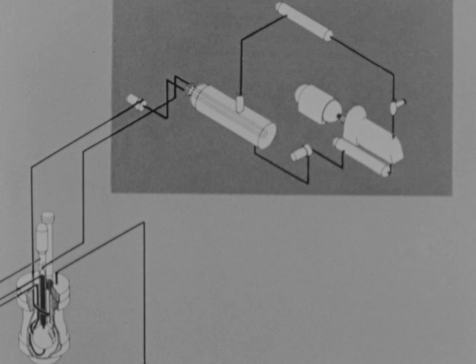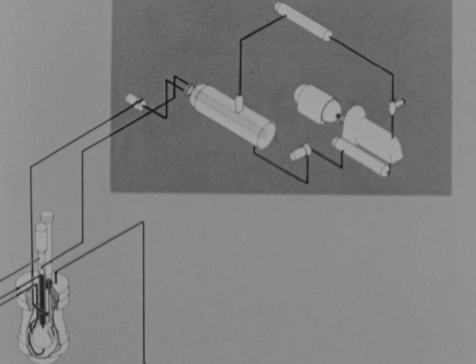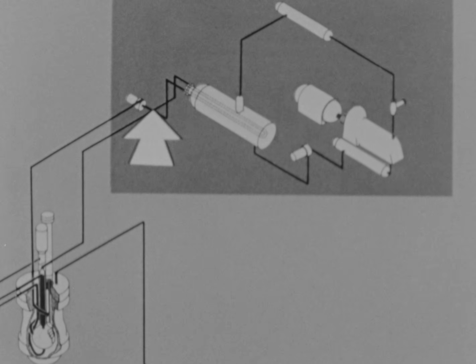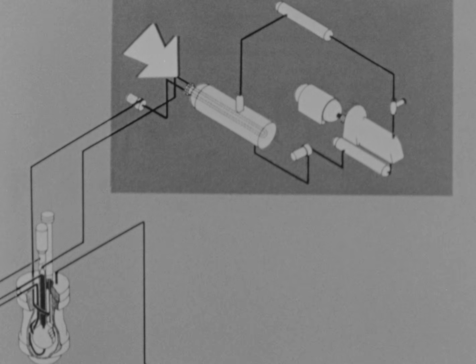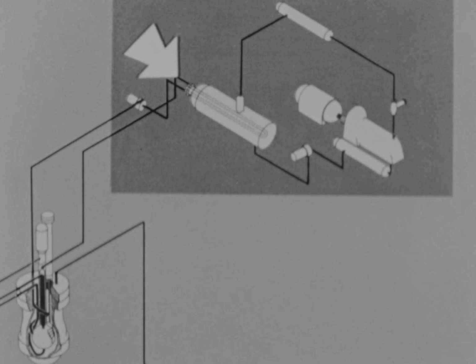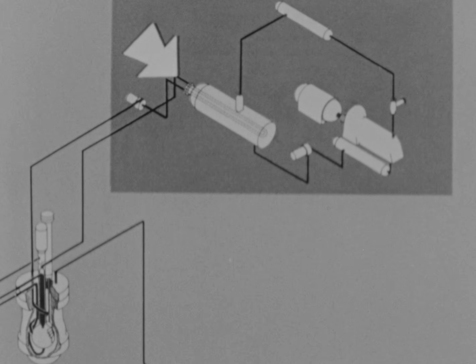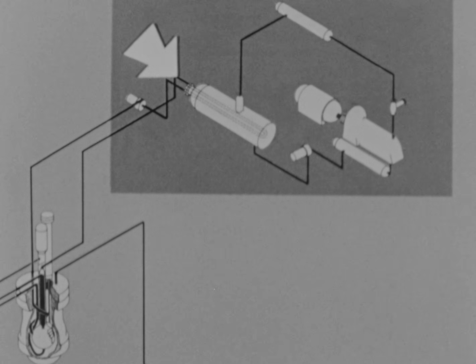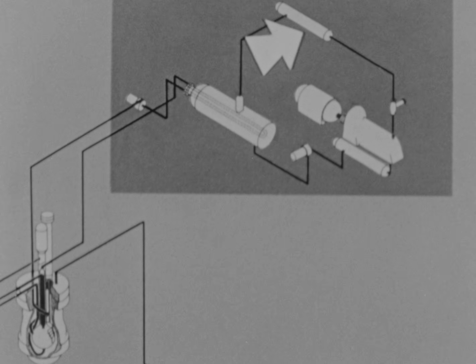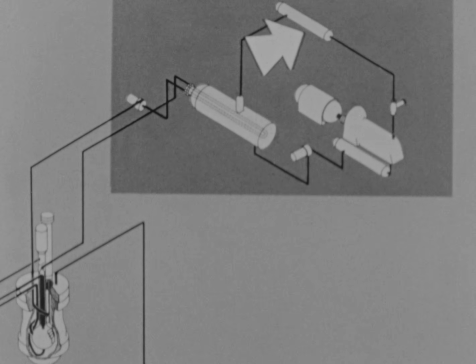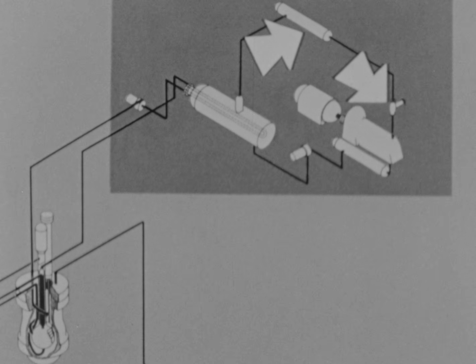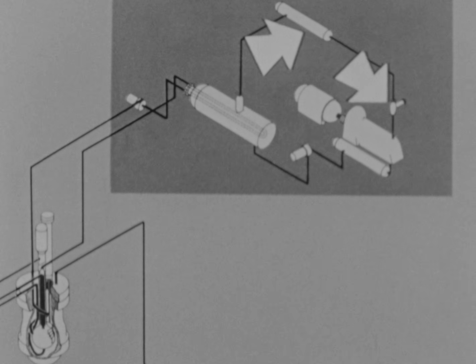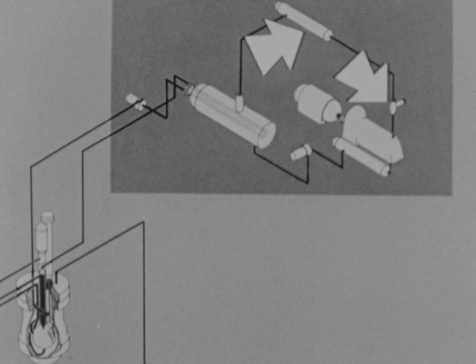In the steam system, the fuel solution, pumped from the reactor at 482 degrees Fahrenheit, carried heat to a heat exchanger. Here, steam was generated at 200 pounds per square inch pressure. This steam passed through a time delay drum where it was monitored for radioactivity, then through a quick closing valve before leaving the shield for the turbogenerator.